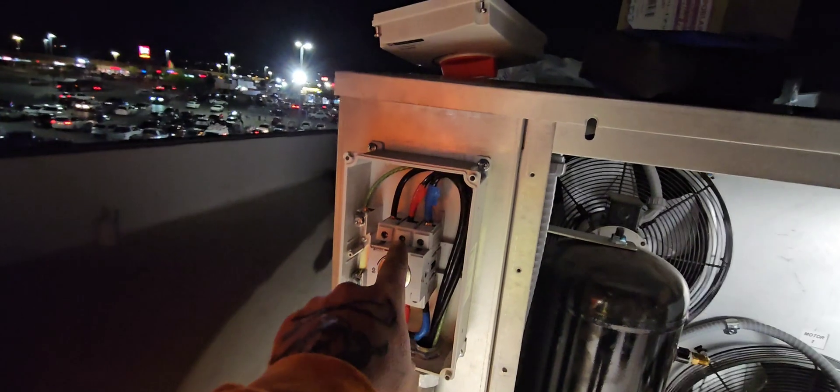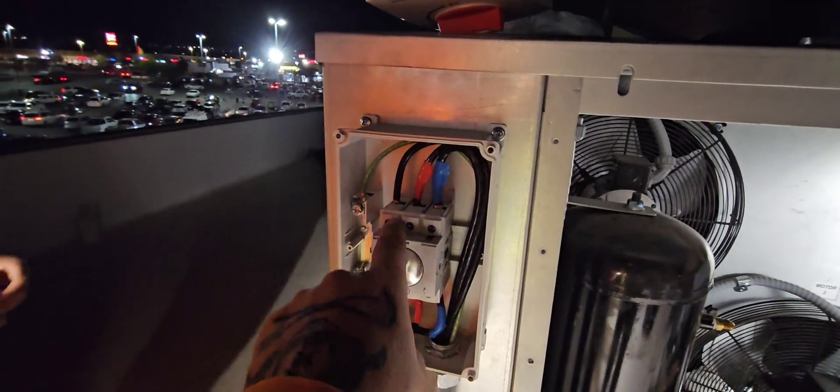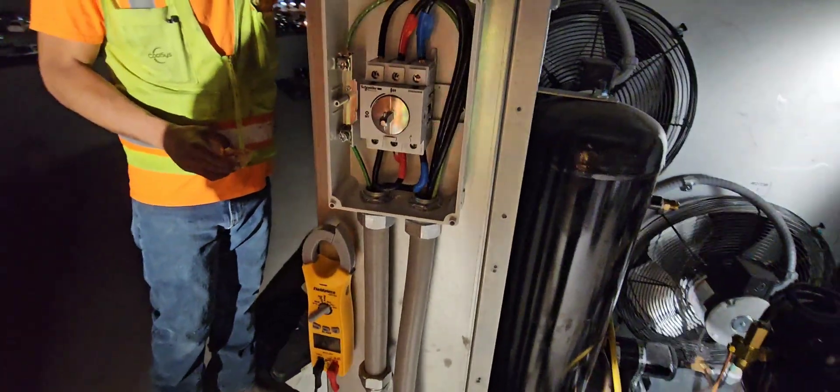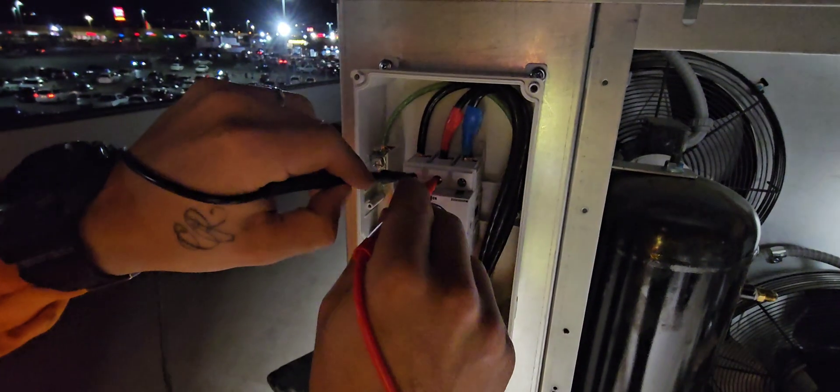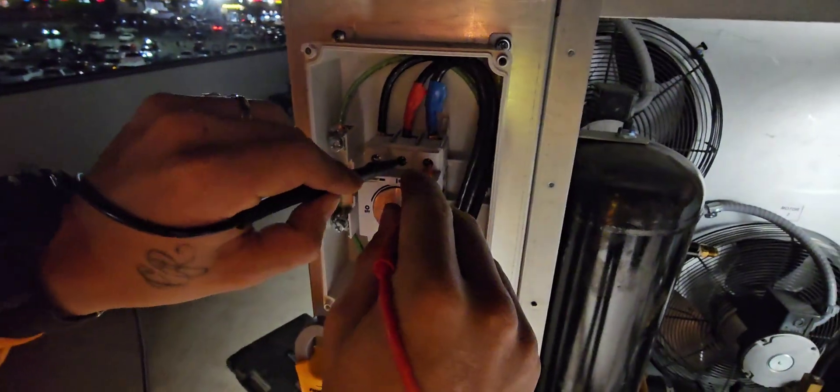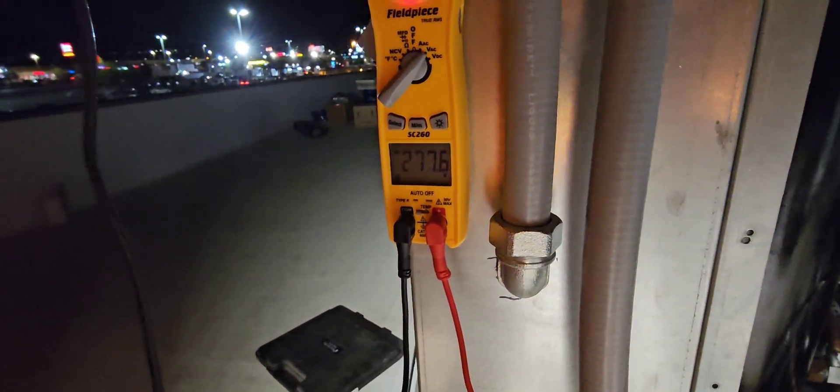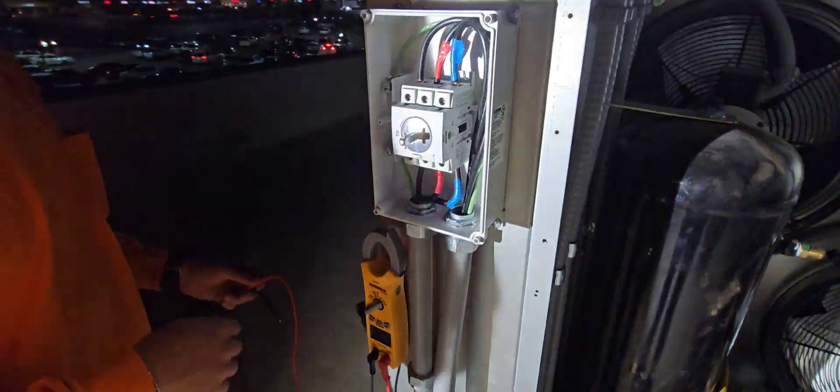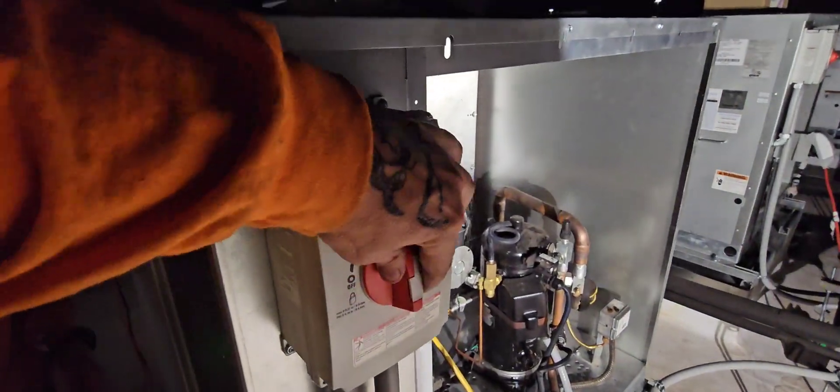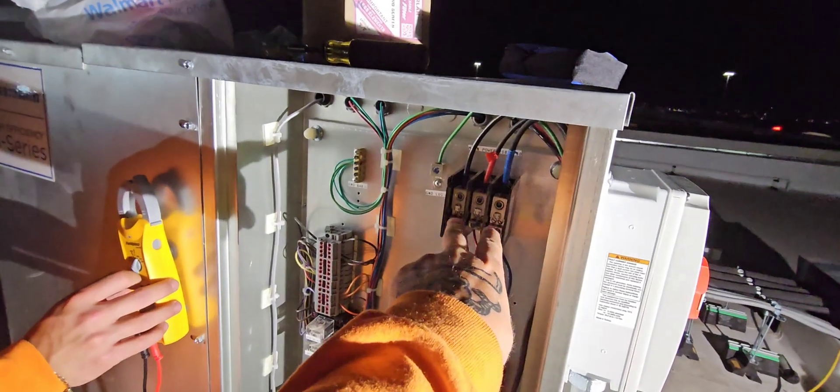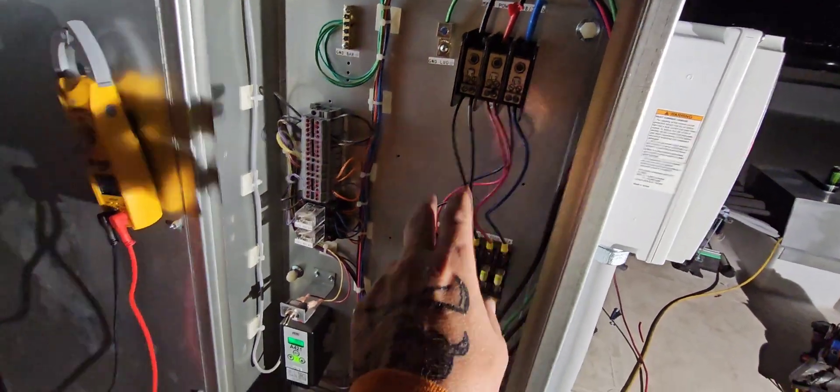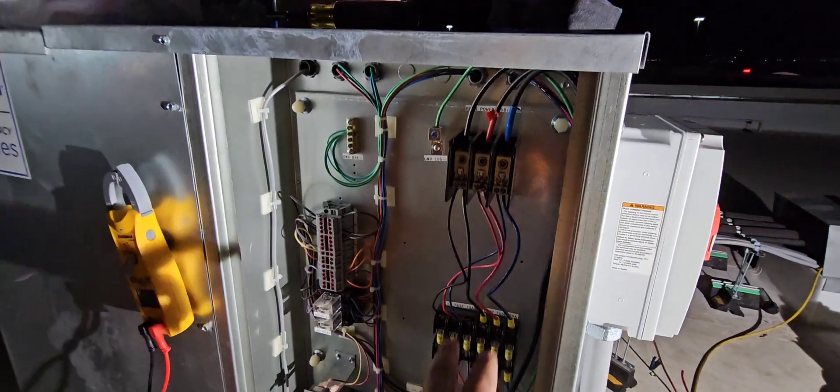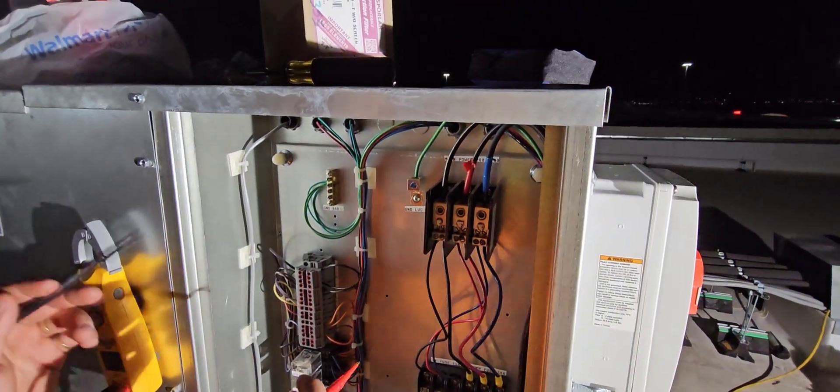We got the whip coming from downstairs landing up top. We're going to check power before we flip this thing on just to make sure that we have power there. We got one to two 208, two to three, and then one to three. We should be good there. We'll slap that cover back on and then turn that on and check power inside.